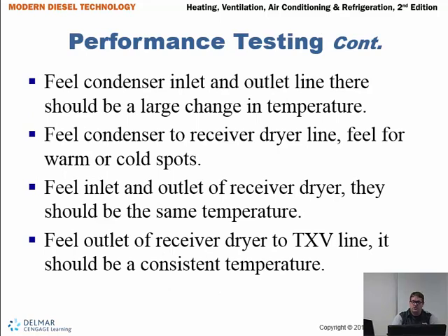Feel the condenser inlet and outlet. There should be a large change in temperature. Feel the condenser to dryer line. Feel for warm and cold spots. What you're looking for there is any restrictions, any unwanted pressure drops, any unwanted resistance.